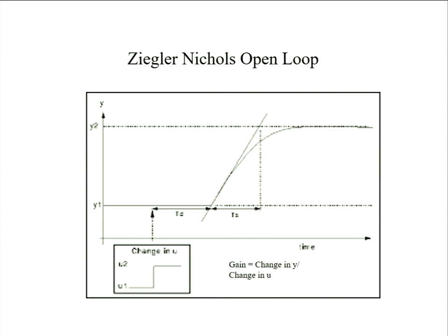So again, I think this was the same process, but this time I've measured that delay, I've measured that rise time, input step size 1, output has to change by 1. In this case, process time delay was 25 units, process time constant was 50. Plug it into the controller and get a response. But again, it is an underdamped, slightly oscillatory response.